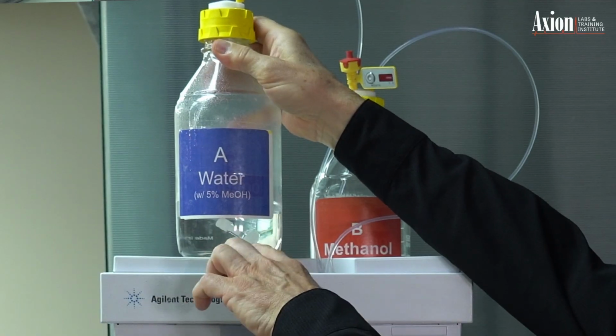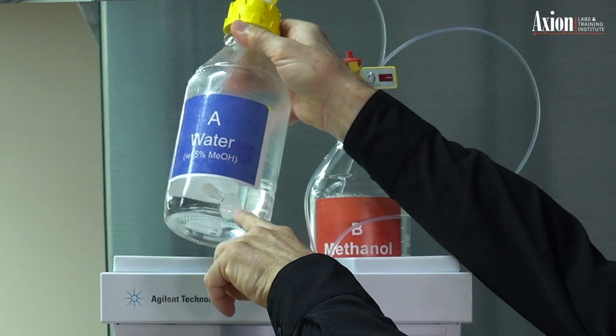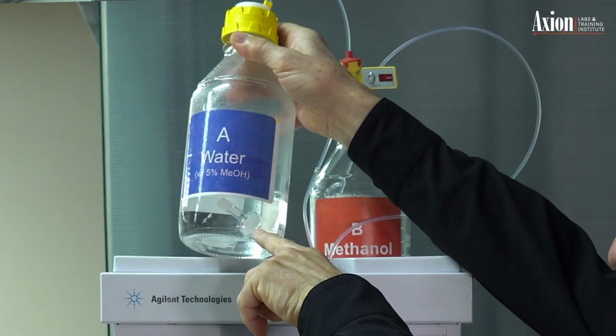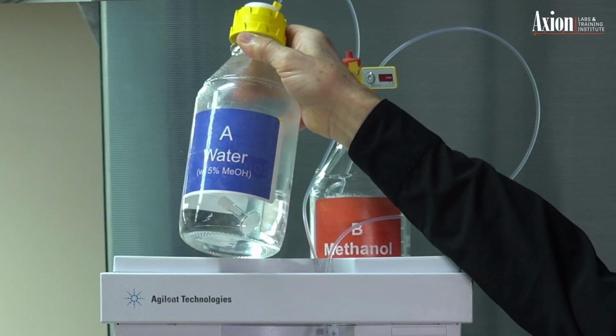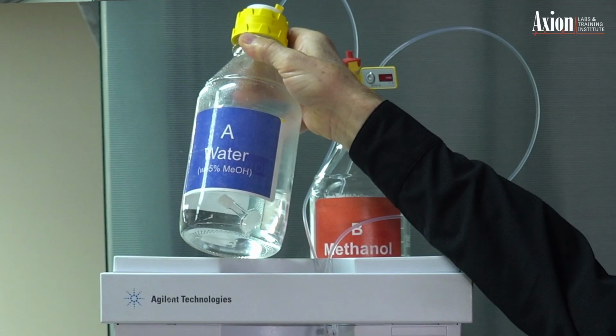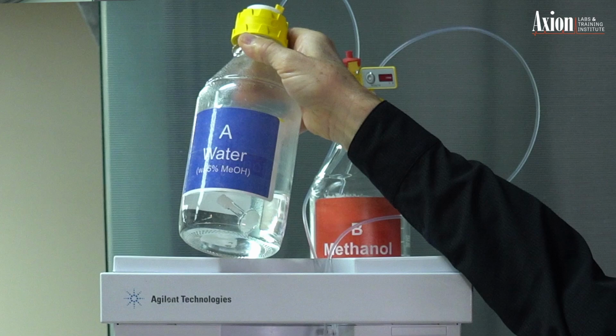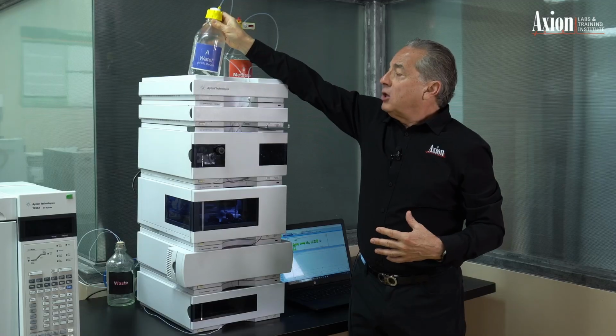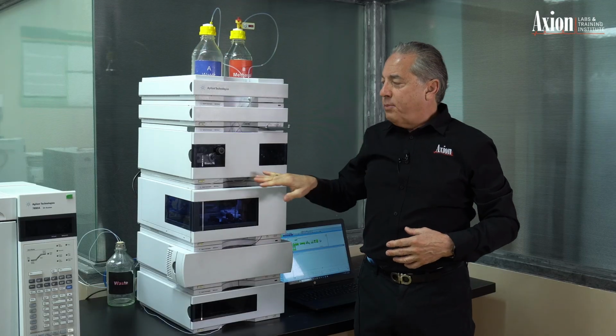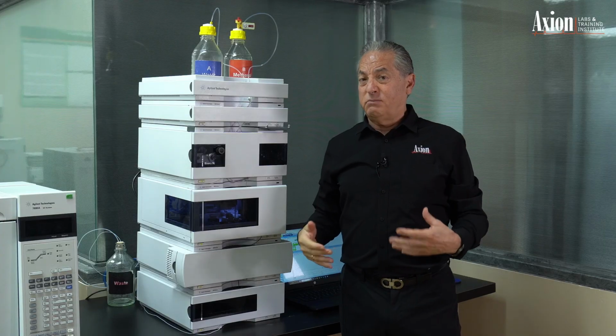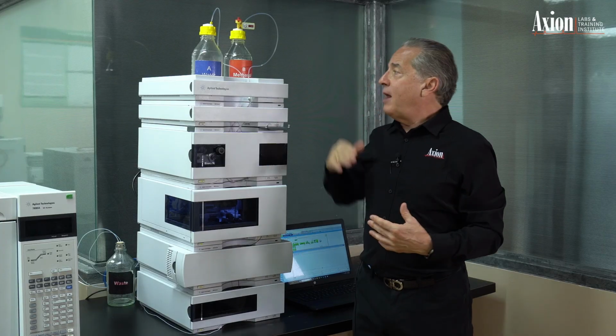So here's my water, and at the bottom of the bottle, you could see a little filter. So that filter is a glass filter. It's about a 10 micron porosity, and it's meant to keep particulates out of the pump. We're going to learn later on that if particulates get into your pump, it could actually do damage, some pretty significant damage. We want to avoid that.